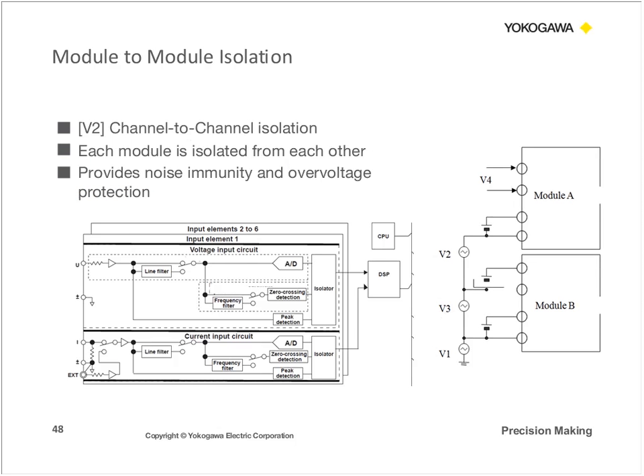The next one is module-to-module isolation. This is great for keeping each of the modules isolated from each other. Many of you are familiar with plug-and-play type modular instruments. This is provided so that you're making all these different types of measurements, whether they be voltage, temperature, strain, or pressure, and these measurements will not be affected by each other when it comes to noise or any transient voltage.